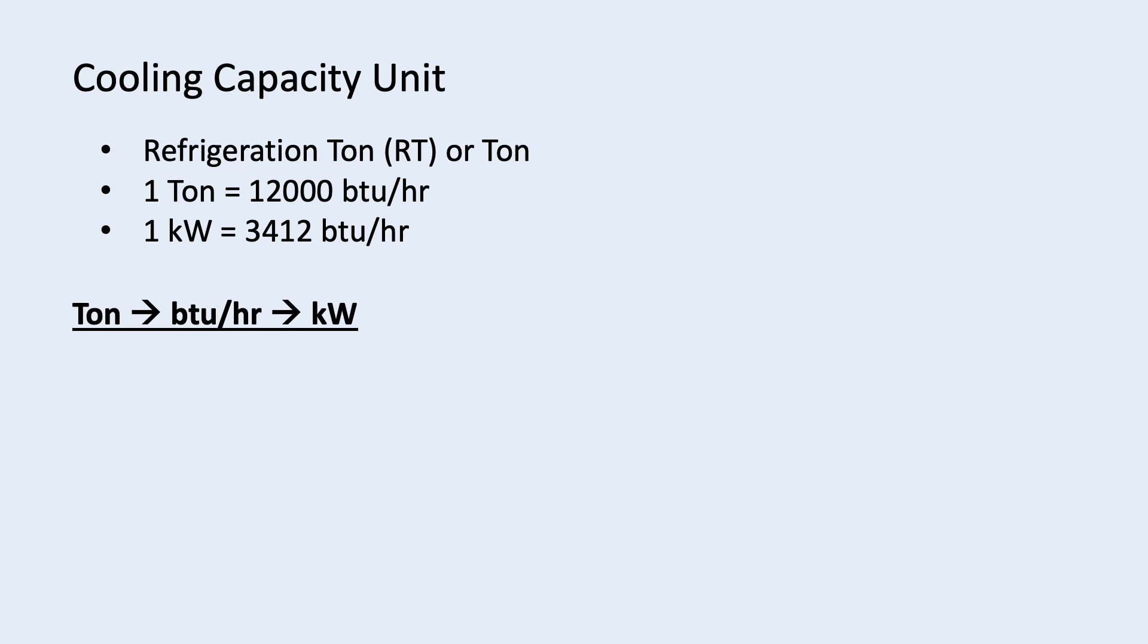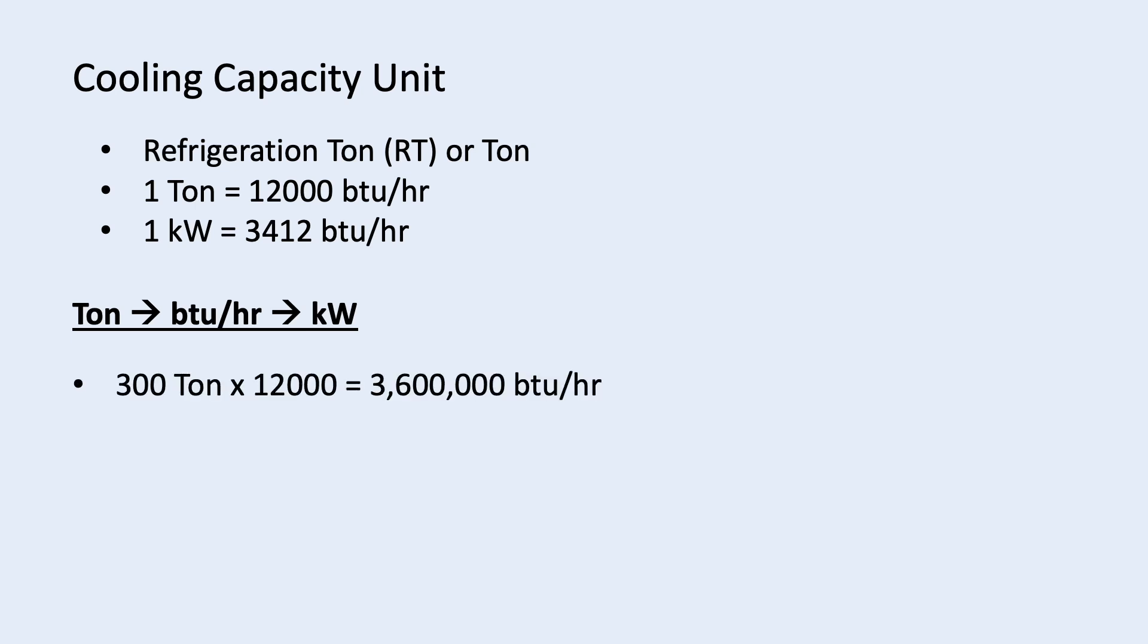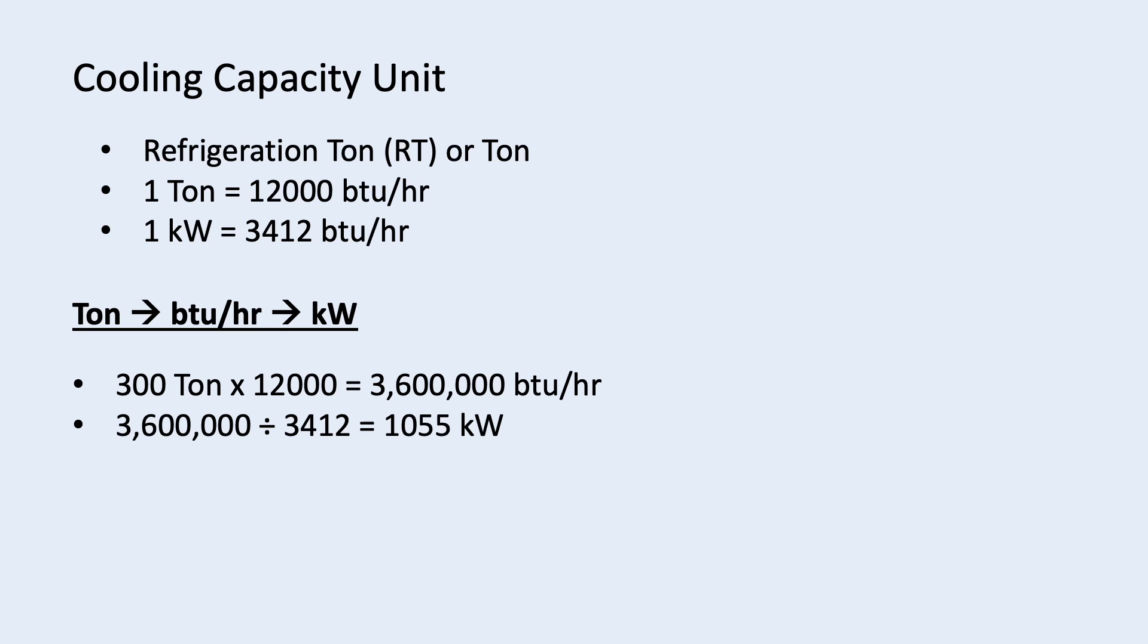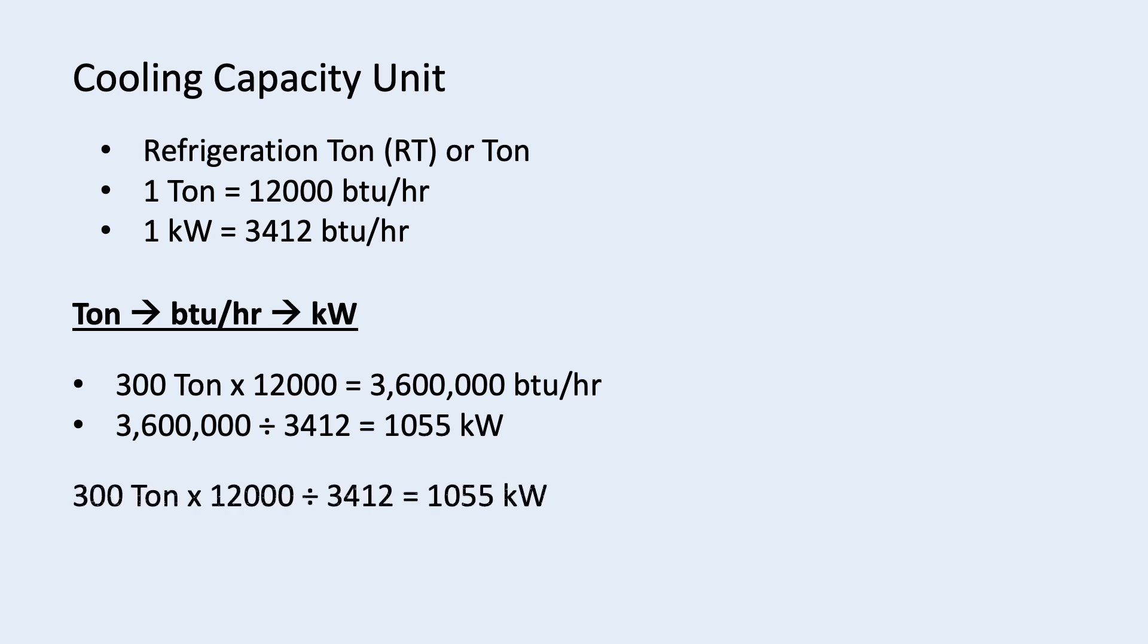So, if you have ton and you want to convert to kilowatt, you first need to convert it into BTU per hour and then to kilowatt. So, 300 ton multiplied by 12,000 equal to 3.6 million BTU per hour. Then, 3.6 million BTU per hour divided by 3412 equals to 1055 kilowatt. So, to convert from ton to kilowatt, we multiply 12,000 and divide 3412.